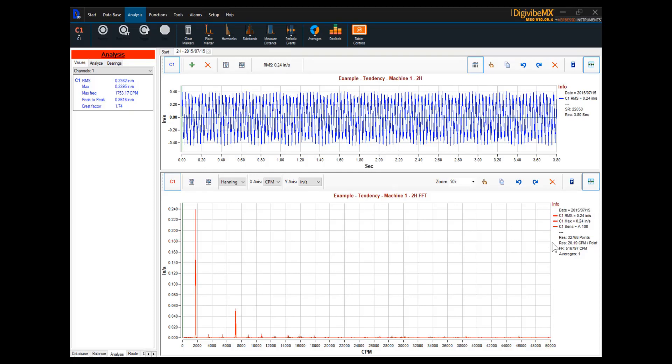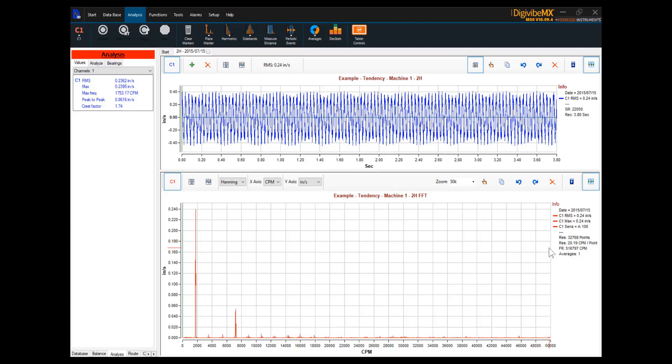At the current resolution of 20.19 CPM per point, we may not be able to differentiate between certain components on the machine. If we're concerned about that, what we can do is increase the resolution. If we have higher speed components that may produce frequencies beyond the current frequency range of 516,797 CPM, we can increase the maximum frequency.